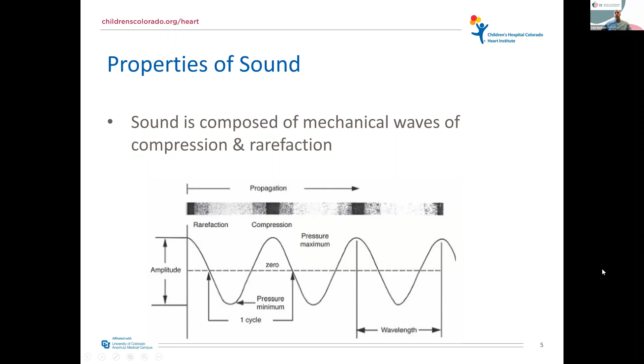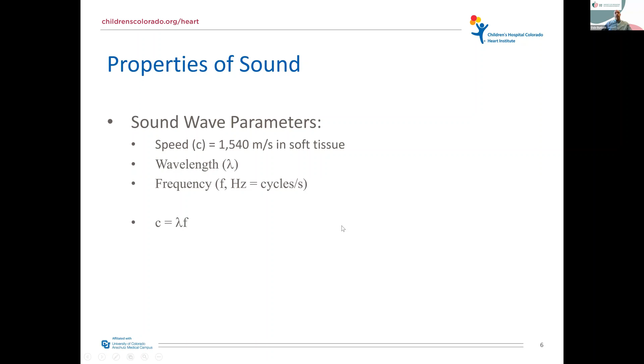It's important to note that sound waves in tissue, which is what we're talking about with echocardiography, move very quickly, 1,540 meters per second. Again, the wavelength is lambda, and frequency is inversely related to wavelength. Frequency is described in hertz, that's cycles per second. How fast the sound is moving is a constant, but how much wavelength there is in a given second is related to the frequency. And so we have different frequency probes. You have a 12, a 9, a 6, a 4, depending on your system, but those refer to the frequency being emitted from the probe itself. So that's the relationship between speed, frequency and wavelength.